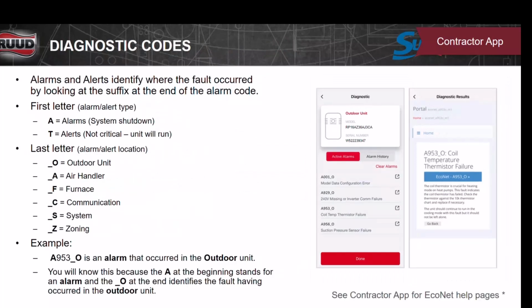Here you see over on the side the O, A, F, C communication. Z, if you had zoning and an airflow problem with the zoning, you get a _Z on the end of it. If you've got an account where the app ties to your Sure Comfort or Ruud app, you click this and it's going to take you into this. This is the code that says this is a suction line thermistor on the outdoor unit, and it's reading out of its parameters. Here are the parameters it should be in. If it's reading out of parameters, then the fix is to change that sensor. It's all going to be there. It's going to point you in the direction you've got to go to help you diagnose the problem with that unit.